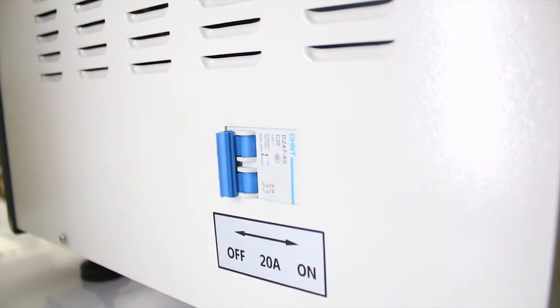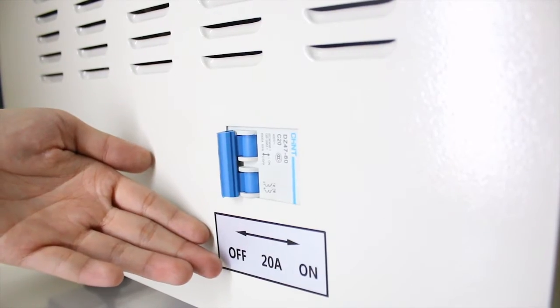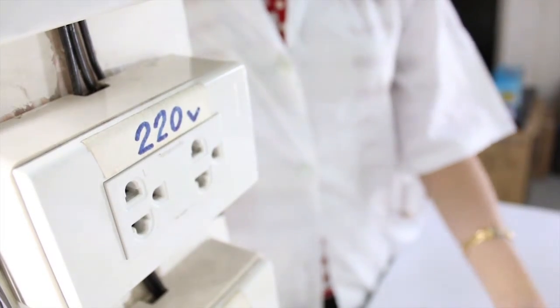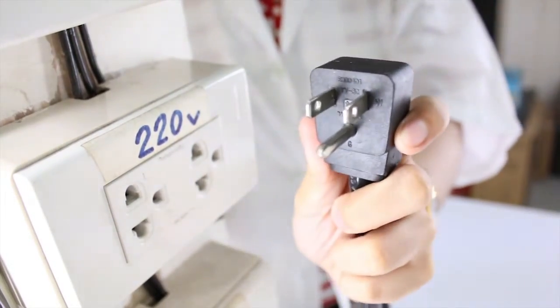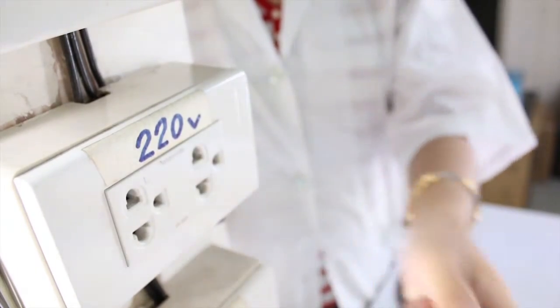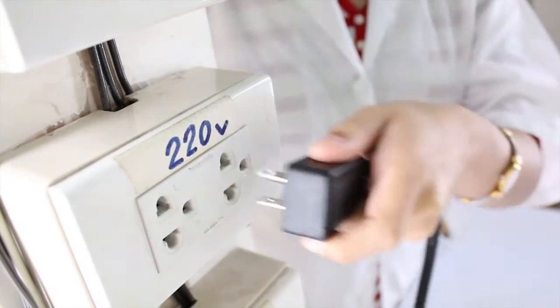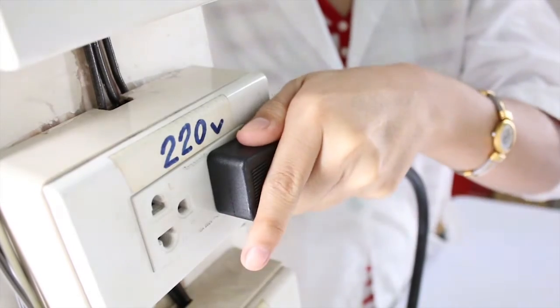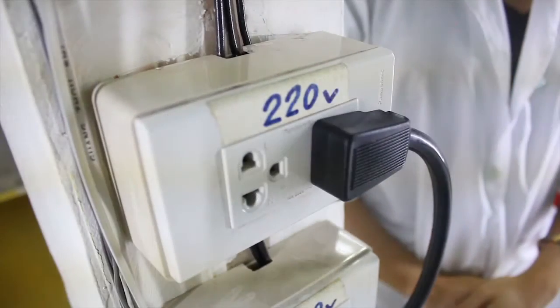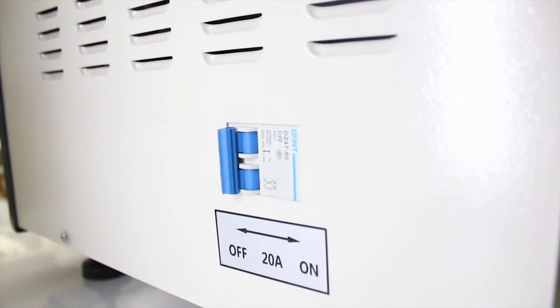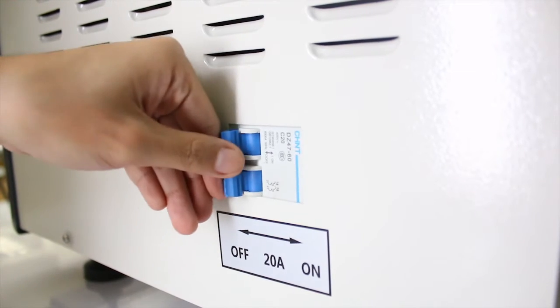The blue switch on the right side of the autoclave is the breaker. Plug the autoclave into a 220-volt 60 Hz outlet. It should be dedicated only for the autoclave. Turn on the blue breaker switch found on the right side of the autoclave.